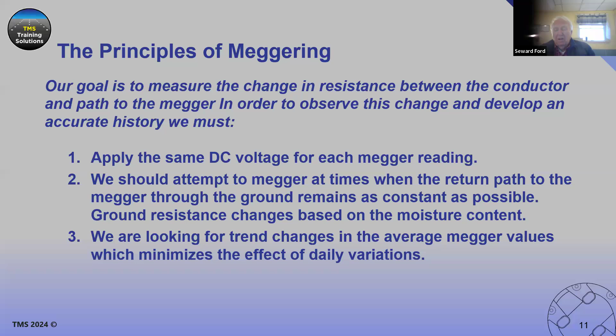But if we take readings at the most appropriate time and over a regular schedule, we then can look at all those readings, and from that we can see a trend developing. Even though we have changes each day, which could be due to the ground resistance changing, if we get a trend over a period of time, we're going to get an indication of what is happening to the resistance from the cable. We're going to get an indication of what the insulation is on the cable and if it's deteriorating or not. That's what we're looking for as we look for a trend over time as we do all these particular readings. Okay, moving on.